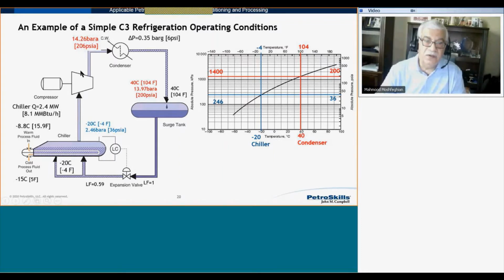the compressor. So the key learning point is the discharge pressure of compressor is set by condensing temperature as well as the pressure drop, and I should say approach temperature as well. The suction pressure of the compressor is set by the chiller temperature. And there is a direct relationship between temperature and pressure for pure component, as you see here for propane.